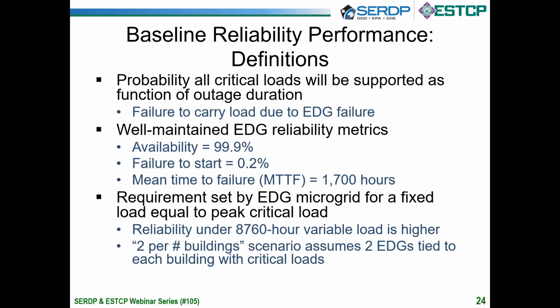We set a minimum performance requirement for this baseline generator to be equal to the reliability provided by this microgrid for a constant fixed load equal to the peak critical load in a year. But I want to also show you what happens when you look at a variable load, which is what we face in reality, and for comparison, show you what happens with the traditional non-microgrid solution when you could afford to put 2 diesel generators on every single building. Now, in fact, I think as most people know, that's not the common solution, but it is done for the most high priority critical loads on military bases.